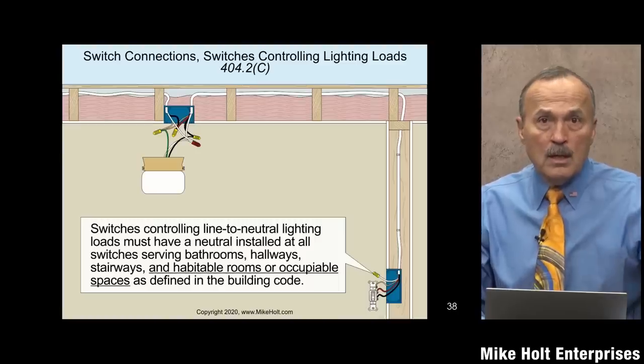We need neutral conductors at switch boxes. If I were building dwelling units, I'd put a neutral at every switch location regardless — even outside lighting switches that don't technically require one. Many modern smart switches now require a neutral. You need to decide what you want to do beyond the minimum code requires.